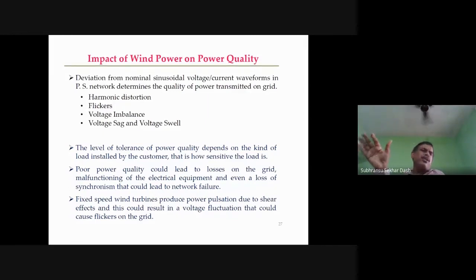There may be harmonic distortions, as I told you, while using the converters. There may be flickers because voltage may change very frequently. There may be voltage imbalance, voltage sag and voltage swell. The level of tolerance of power quality depends on the kind of load installed by the customers, that is, how sensitive the load is. Poor power quality could lead to losses in the grid.